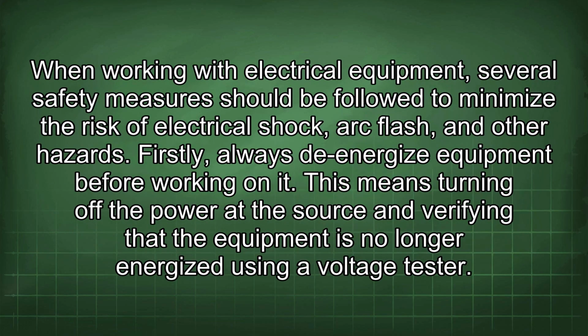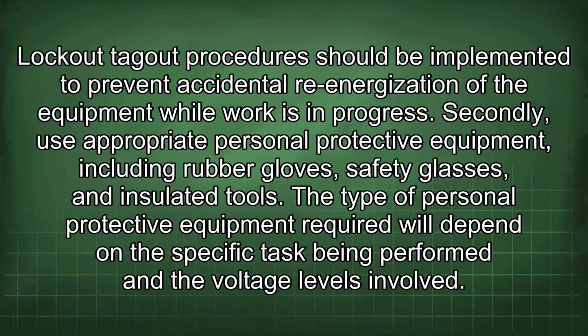When working with electrical equipment, several safety measures should be followed to minimize the risk of electrical shock, arc flash, and other hazards. Firstly, always de-energize equipment before working on it. This means turning off the power at the source and verifying that the equipment is no longer energized using a voltage tester. Lockout-tagout procedures should be implemented to prevent accidental re-energization of the equipment while work is in progress. Secondly, use appropriate personal protective equipment, including rubber gloves, safety glasses, and insulated tools. The type of personal protective equipment required will depend on the specific task being performed and the voltage levels involved.